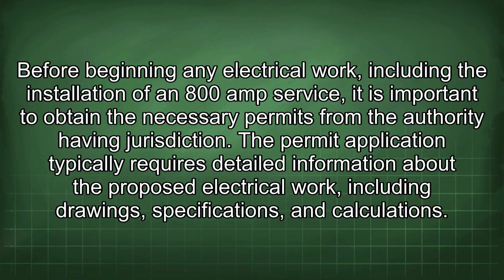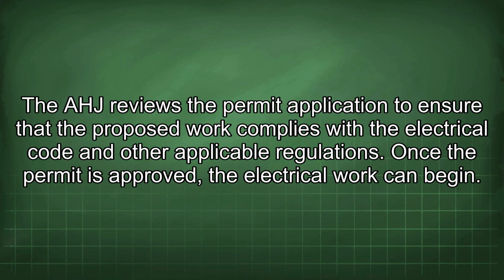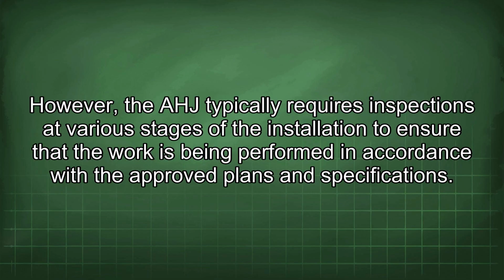Before beginning any electrical work, including the installation of an 800 amp service, it is important to obtain the necessary permits from the authority having jurisdiction. The permit application typically requires detailed information about the proposed electrical work, including drawings, specifications, and calculations. The AHJ reviews the permit application to ensure that the proposed work complies with the electrical code and other applicable regulations. Once the permit is approved, the electrical work can begin. However, the AHJ typically requires inspections at various stages of the installation to ensure that the work is being performed in accordance with the approved plans and specifications.